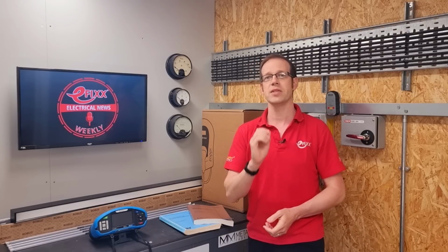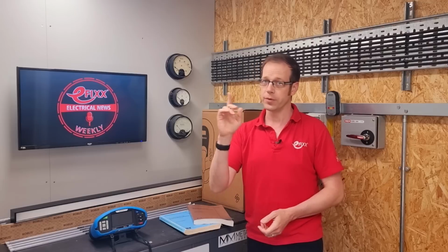The experts at Bureau Veritas also recommend that electrical contractors see these regulations as a minimum standard to work from, not up to, and that things like full testing of RCDs is still a best practice approach to ensure maximum safety and mitigate risk.